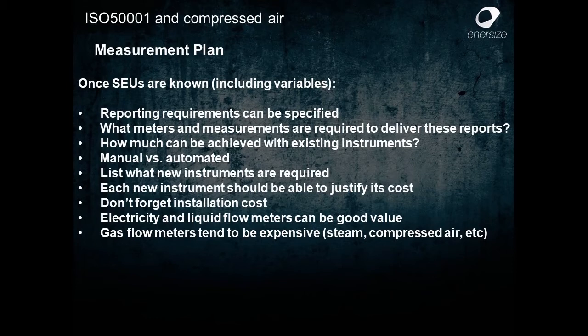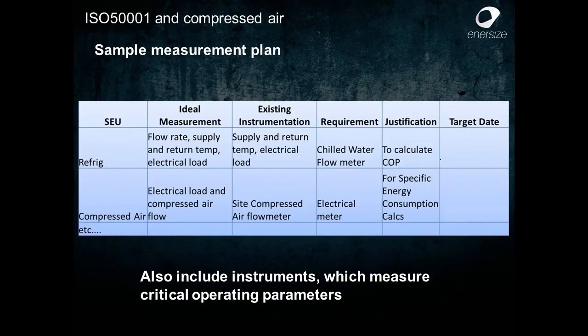The sample measurement plan could look like this. I just brought into this plan refrigeration, where the ideal measurements could be flow rate, supply and return temperature, and electrical load. And we look into what existing instruments we have already. And the requirement will be a chilled water flow meter, simply because we want to calculate the performance indicator for a refrigeration plant, the so-called COP, coefficient of performance.